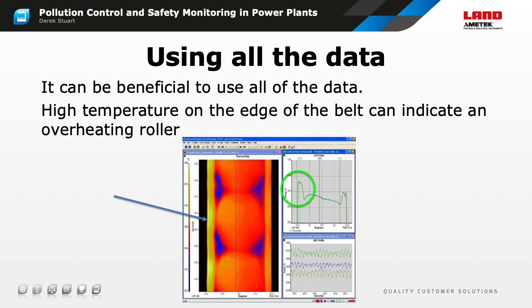Using all of the data allows the operator to see exactly what's going on and especially allows him or her to establish zones of interest within the image. In this example, we are measuring both the temperature of the material on the belt in the central area and the temperature of the edge of the belt. This allows us to detect an overheating edge, which usually occurs when a bearing is not running correctly and is causing a lot of friction. At least one biomass fire is thought to have been caused by an overheating bearing.